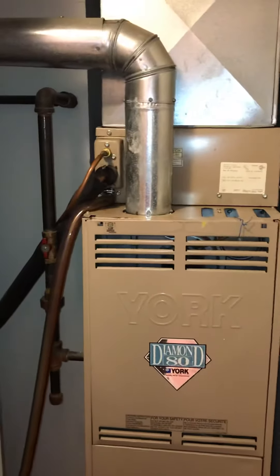It's a 40-inch furnace, and from the top of the furnace to this wall — it's actually not drywall, it's metal painted white — we have 32 inches, actually closer to 36. As far as access is concerned, we're close to the front door, so we'll need floor coverings down and will probably take off the sliding door to give ourselves some room.